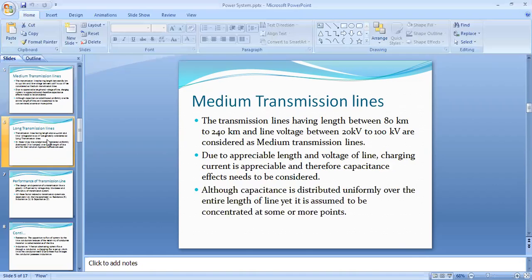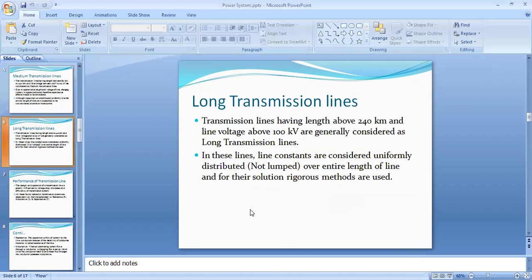What is the long transmission line? Transmission lines having a length above 240 km and a line voltage above 100 kV are generally considered long transmission lines. In this type, line constants are considered uniformly distributed over the entire length of the line, and their solution uses the rigorous method.